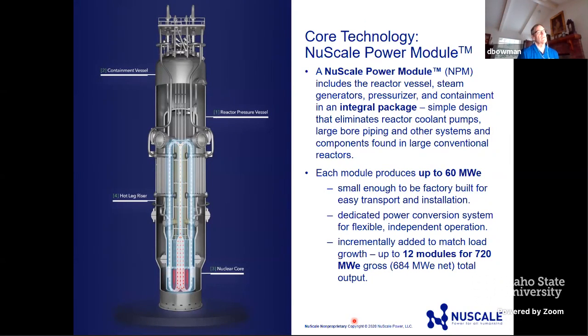The real technology is we're still a pressurized water reactor. So we use light water as a moderator. We still use boron as a fission poison, which is pretty much in line with what traditional pressurized water reactors use. The real difference is we're small, only about 60 megawatts electric compared to a large traditional PWR. The two I was licensed at, they were in excess of 1,000 megawatts of electrical output, and their thermal output was over 3,000 megawatts.